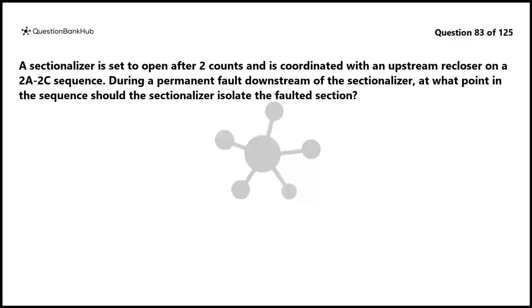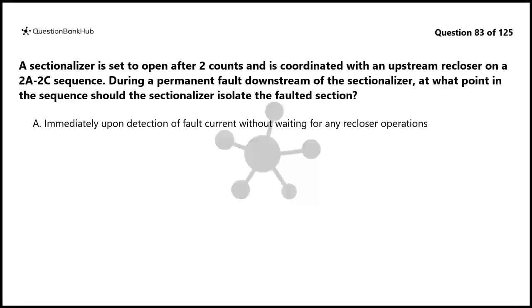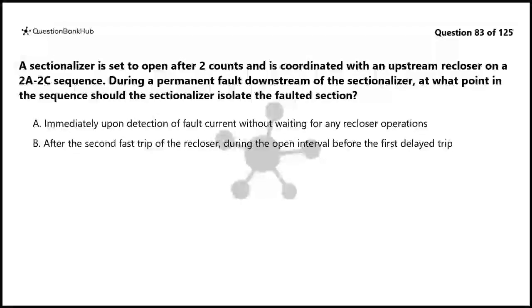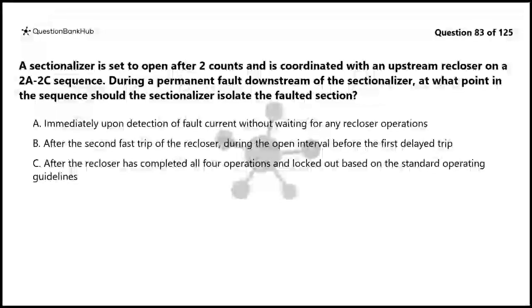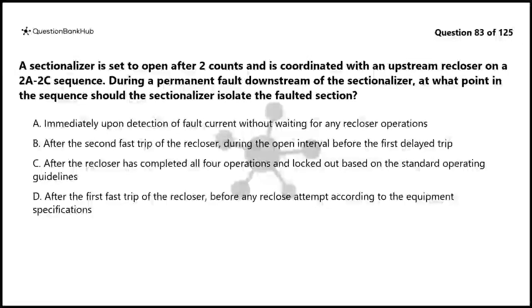Question 83. A sectionalizer is set to open after 2 counts and is coordinated with an upstream recloser on a 2A, 2C sequence. During a permanent fault downstream of the sectionalizer, at what point in the sequence should the sectionalizer isolate the faulted section? A. Immediately upon detection of fault current without waiting for any recloser operations. B. After the second fast trip of the recloser, during the open interval before the first delayed trip. C. After the recloser has completed all 4 operations and locked out based on the standard operating guidelines. D. After the first fast trip of the recloser, before any reclose attempt according to the equipment specifications.